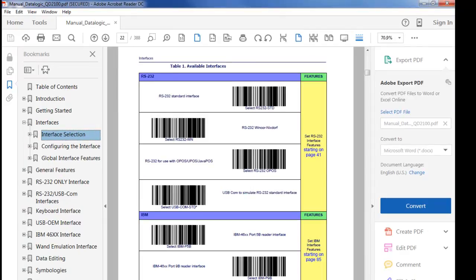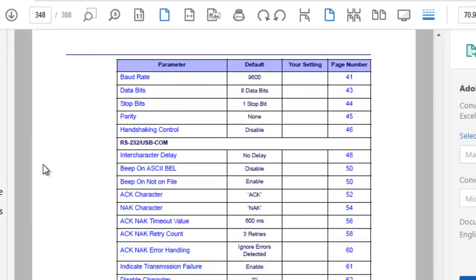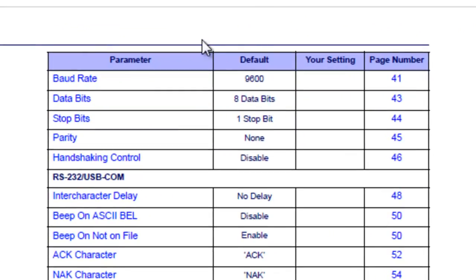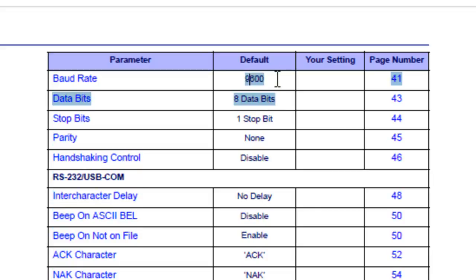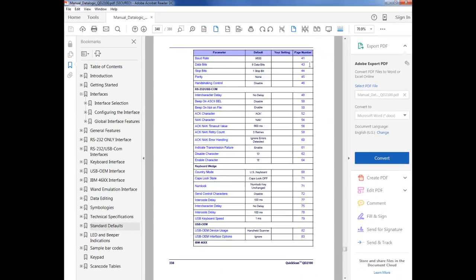Also in the manual, we can then go to Appendix B for the default values for the baud rate, data bits, stop bits, and parity for that COM port once it's emulated. So I've got 9600 baud, eight data bits, one stop bit, no parity, and no handshaking control. I need to remember those for when I'm configuring my COM port in OmniServer later.